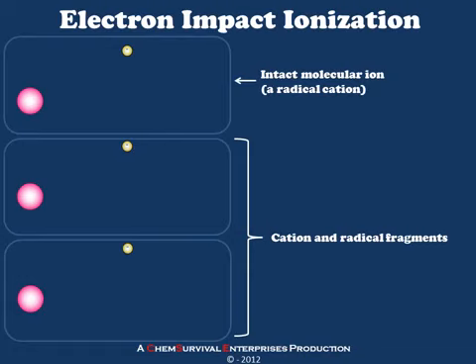Let's begin by considering how to ionize a molecule. I'll be showing you one of the most basic but most widely used ionization methods in mass spectrometry: electron impact ionization. In electron impact ionization, the gas phase molecules are passed through an arcing electrical current, which consists of very high energy electrons. On occasion, one of these high energy electrons will strike the molecule, creating a radical cation by knocking a second electron out of the outer shell of that molecule as it passes by.